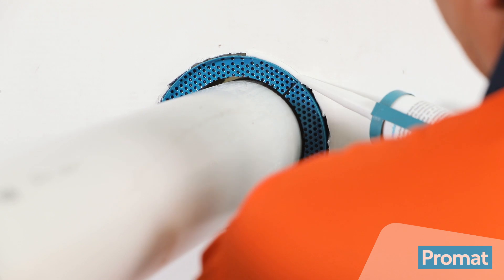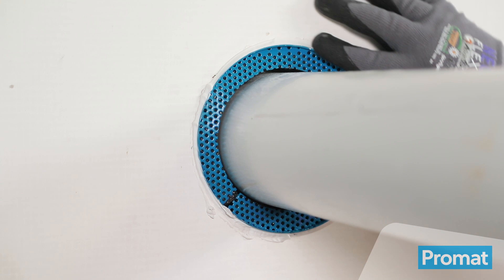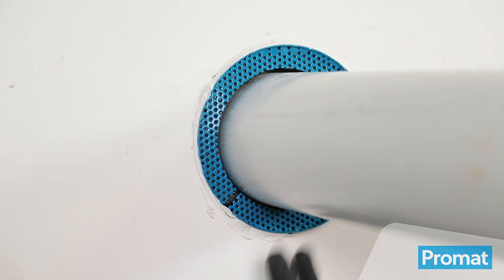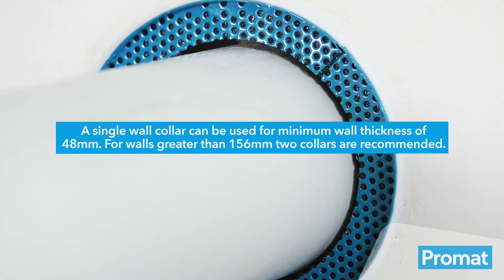When sealing gaps, ensure you do not obstruct the perforated mesh at the end of the collar. Ensure the gap between the wall and collar is no greater than 20 millimetres. Refer to the appropriate collar selector and test reports for more information.